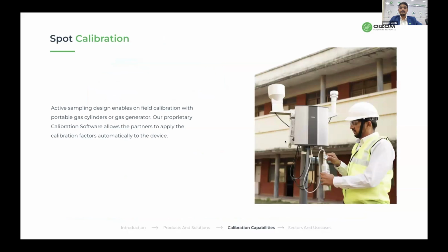Because we use active sampling, we can do on-field calibration using portable gas cylinders, which are SI traceable gases with standard certifications. We offer the calibration software and the calibration hood and kit to our partners so they can do the calibration on site themselves. Throughout this process, your project managers will be there with you, and an environmental person will also help with any troubleshooting or support you require.